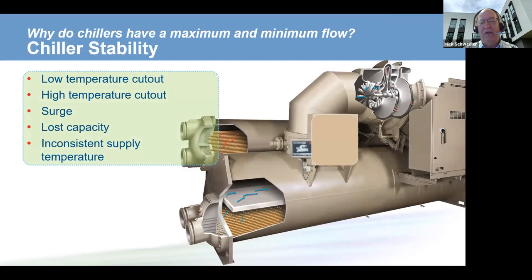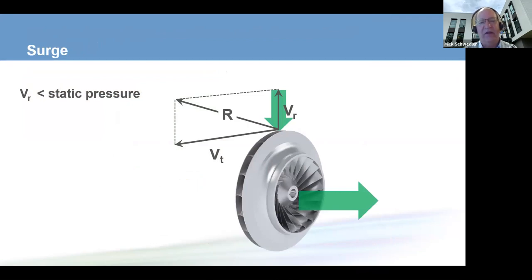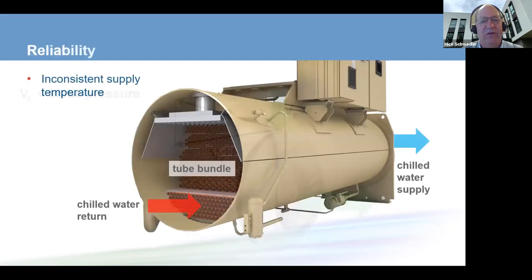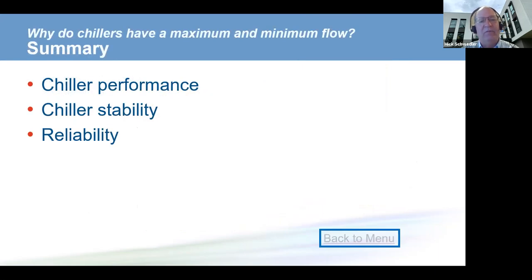So if any of these issues happen because we go below the minimum flow rate, we have chiller instability. We also can have that surge that I discussed. And that is where the refrigerant pressure in the condenser actually pushes the refrigerant backwards through the compressor. If you've ever been in a chilled water plant where the chiller surges, you know two things. One, it's not good. Two, you want to get out of the plant because it's screaming like a banshee or it's shaking. You don't want to operate those chillers in surge. So we talked about the minimum and maximum flow rates, stay between them. The manufacturer will tell you what they are for a specific chiller. You want to have good performance from an efficiency standpoint, stability and reliability for that chiller.